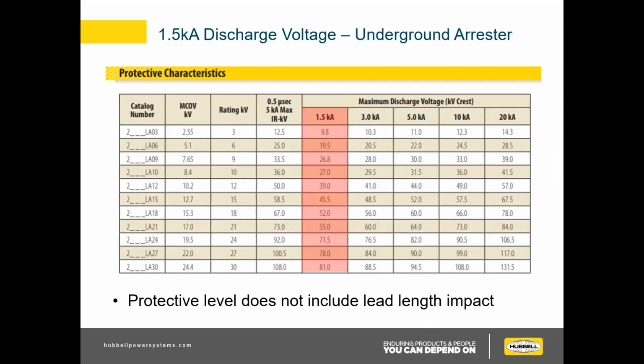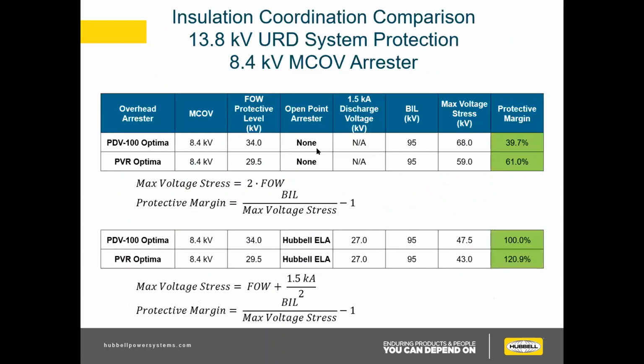Bear with me. Here are your discharge voltages for your elbow arrestor, and once again, it does not include lead length impact. It's a lot to keep track of when you're doing this, but it's super important. You can have an arrestor in the system and it ends up not protecting your equipment because you have too much lead length, which would kind of stink. Here we have a lot going on. This is just the calculations that were mentioned in the past couple slides. But the most important thing to look at here is your protective margin.